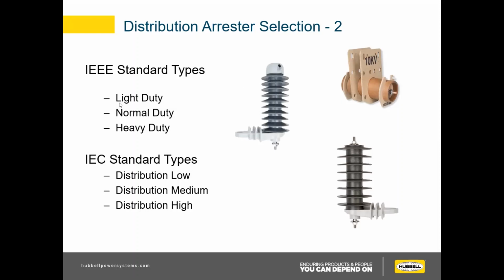But our normal duty would be a PDV 65, like I said, and then our heavy duty can be broken out into 2 types: our PDV 100, which is just a heavy duty, and our PVR, which is a riser pole application. The weird thing is they're both tested to the same amount, but the riser pole is specialized, and we'll go over that in a few minutes. And then we have our under oil arrestors, which are mainly sold to OEMs for transformers. They're under oil in the transformer can. I honestly don't know a ton about them, but we do sell those as well. I believe those are the PV 65 blocks, so very similar discharge voltages in that case.